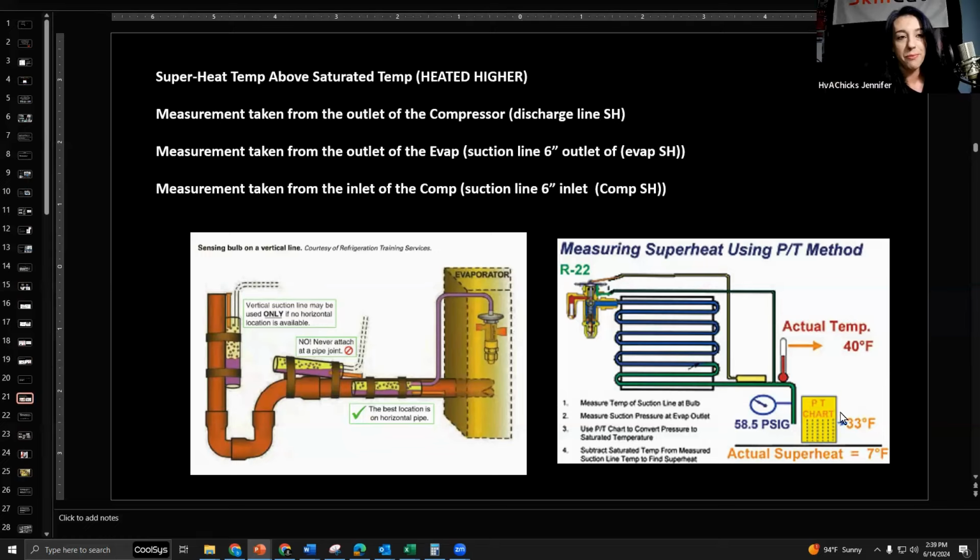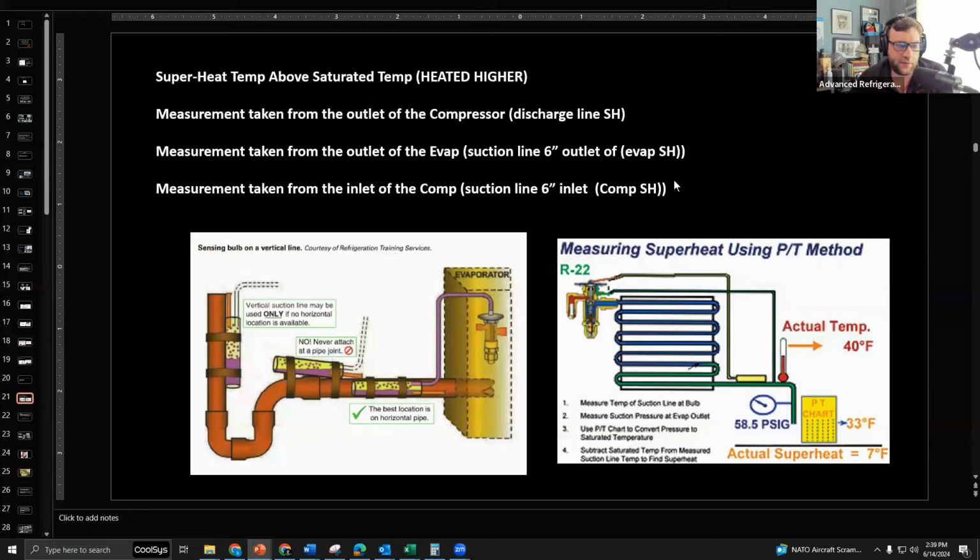Let's see what else we got. Can I say something about the saturation temperature that you were touching on a second ago? Please do. I come from a residential world where everybody's real eager to hook up their gauges. What we are pushing over at Tech is that if you take your saturation temperatures, you take your line temperatures and use your rules of thumb with your condensing 20 to 30 above ambient, you can get away from hooking up and kind of figure stuff out and being non-invasive. And I think that's very important. Non-invasive system check. We preach it. Kind of wish I got there sooner, right?